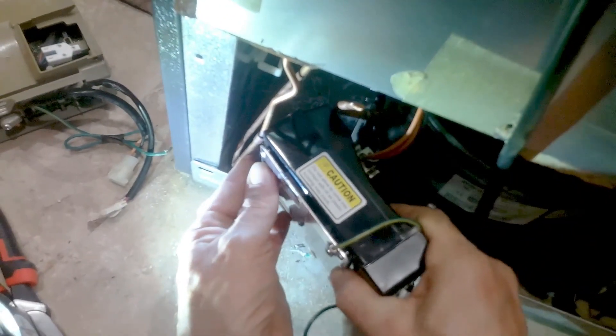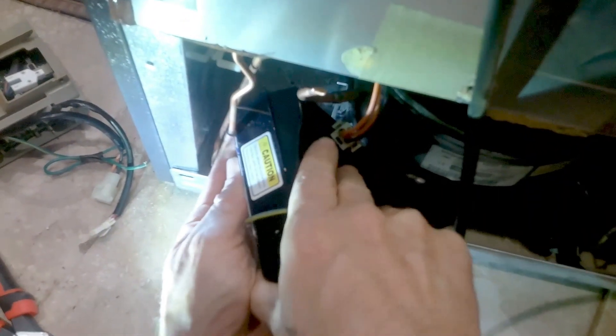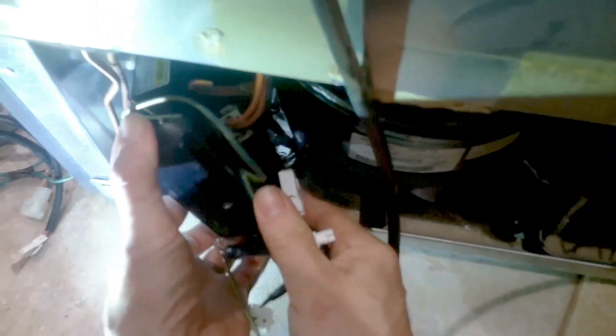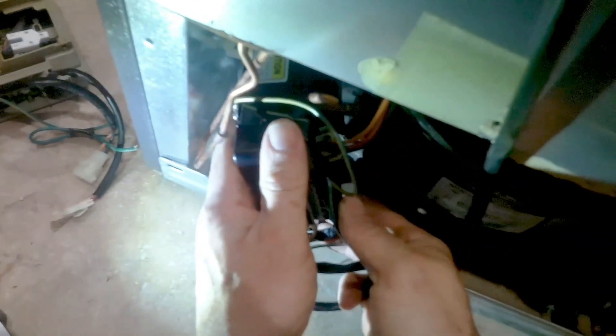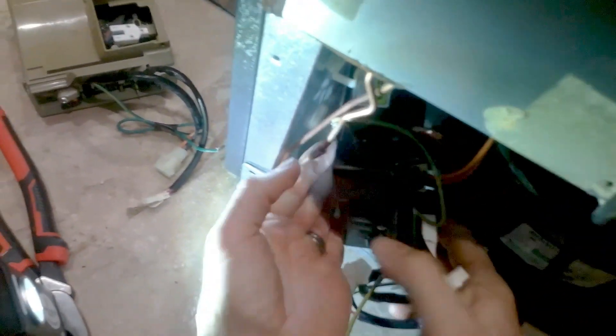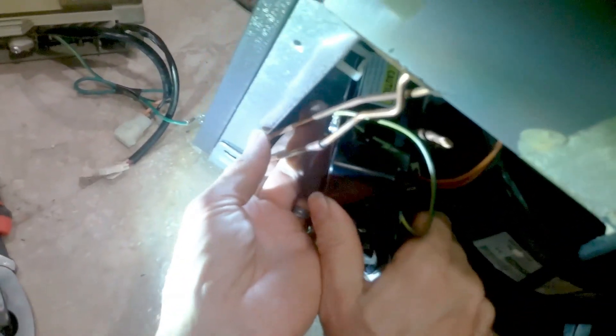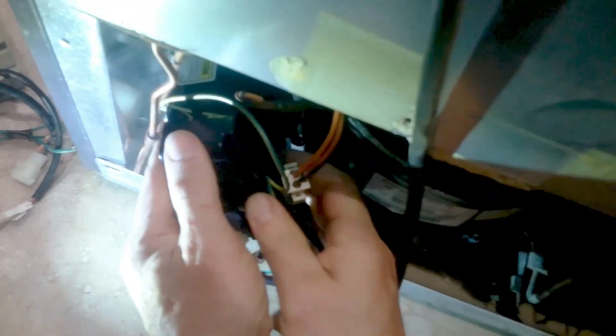First, align and find where the hole is on the inverter so you know exactly how to slide it in, since you'll need to put the quarter-bit screw back in place. Just gently press it in — you can press on the copper tubing on the left a little bit if you have to, but not too much. Take your time until you get it in there correctly.